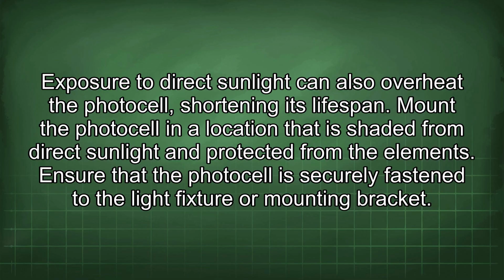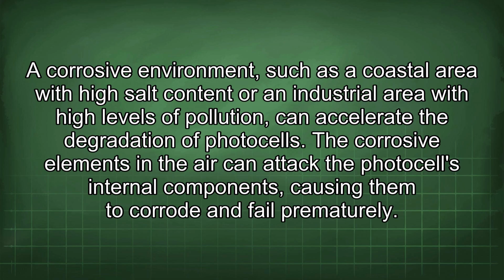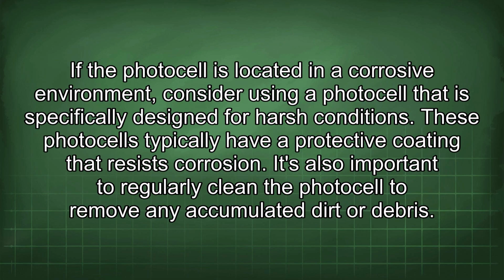Ensure that the photocell is securely fastened to the light fixture or mounting bracket. A corrosive environment, such as a coastal area with high salt content or an industrial area with high levels of pollution, can accelerate the degradation of photocells. The corrosive elements in the air can attack the photocell's internal components, causing them to corrode and fail prematurely. If the photocell is located in a corrosive environment, consider using a photocell that is specifically designed for harsh conditions. These photocells typically have a protective coating that resists corrosion.